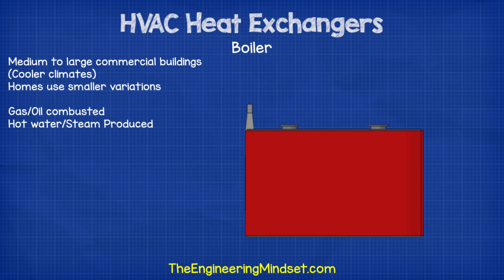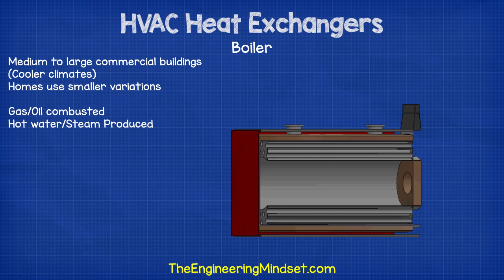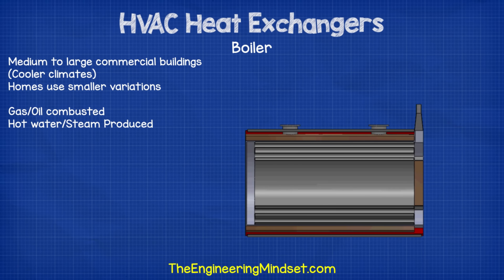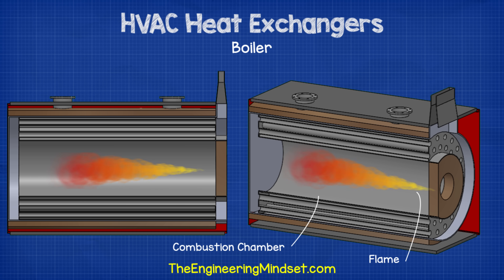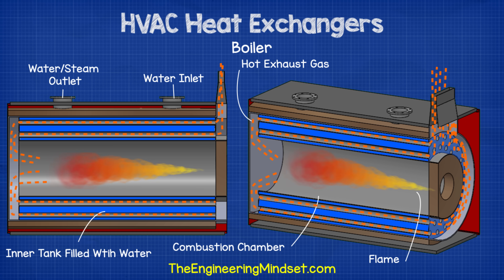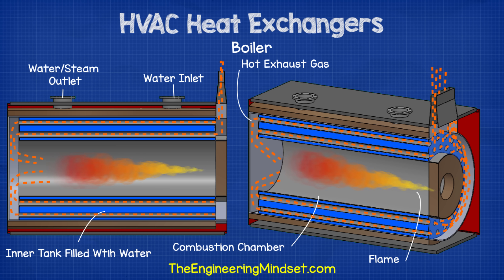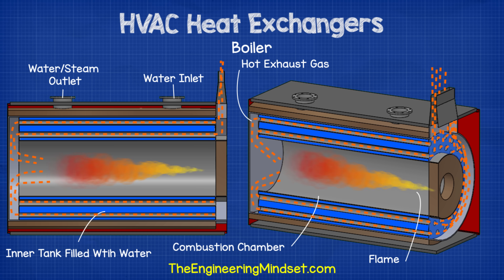Large water boilers are found mostly in medium to large commercial buildings in cooler climates, with smaller wall-mounted versions for homes. Fuel is combusted in the combustion chamber — usually gas or oil — and the hot exhaust gases are forced through a number of tubes until they reach the flue and are released to the atmosphere. The tubes are surrounded by water; heat convects to the tube walls and conducts through into the water, which is then carried away by convection as either heated water or steam. A pump forces the water through, and its speed and fuel combustion rate can be varied to change temperature and flow rate.